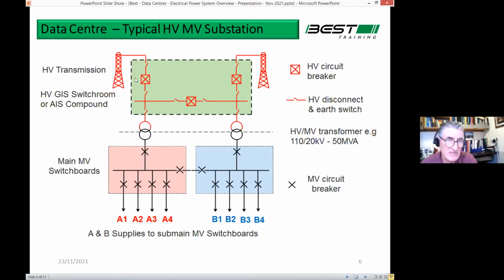So what you're seeing inside the green box is the connection of one pylon coming down through a circuit breaker, that's the box with the X in it, and the other switches are what they call high voltage disconnects, to be able to isolate the circuit breaker. So you have a circuit breaker on each side, and then both supplies are coupled through this arrangement here. So it gives the ESB flexibility to do different switching operations.